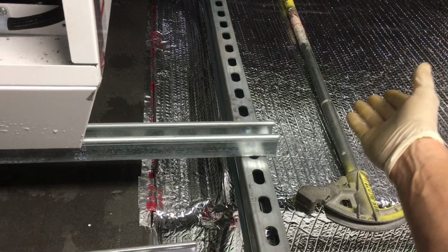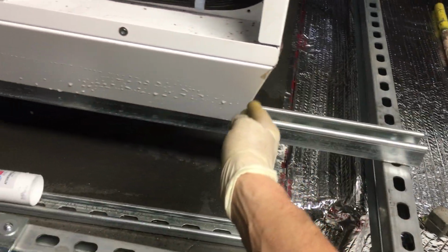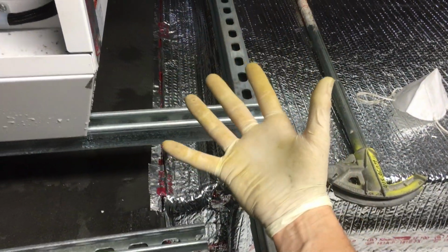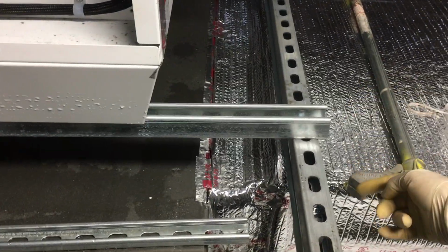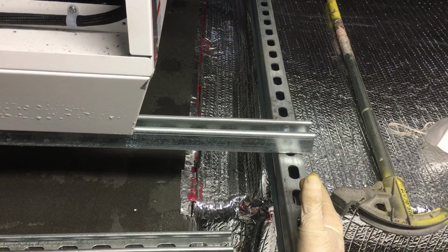So if you wanted to keep the room at 70 degrees or 80 degrees at nighttime, you run the air conditioning, and you take that waste gas and you heat water, and for nearly free, other than some water piping and a small pump, you run it through a coil and you reheat your air.